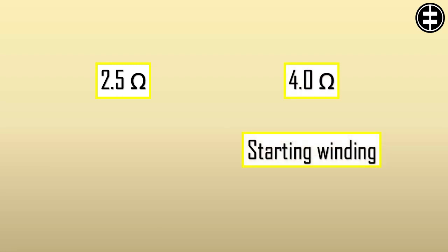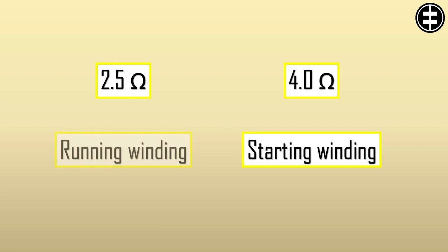In our case, one winding is 2.5 ohms and the second one is 4 ohms. The higher ohm value winding is the starting winding, and the other one is the running winding.